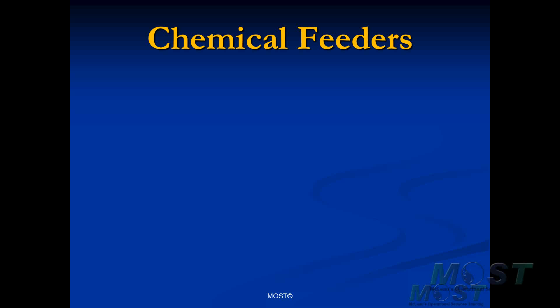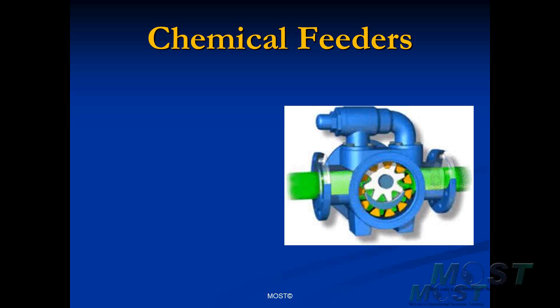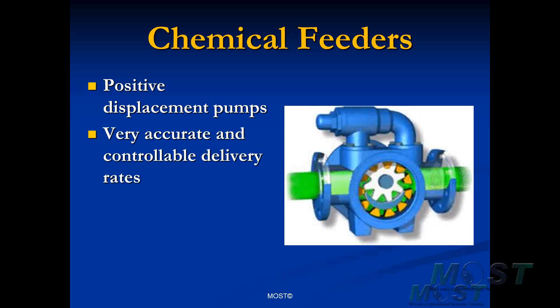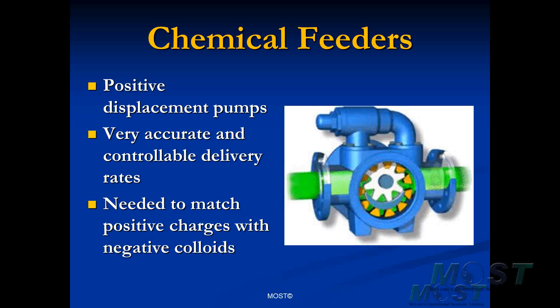To add our primary coagulant to the water, we need a chemical feeder. The typical chemical feeder used for primary coagulants is a positive displacement pump. The reason we choose positive displacement pumps is because they have very accurate and precise delivery rates, and they can be controlled over a wide range of flows. That means that we can deliver exactly the number of positive charges needed for charge neutralization to offset or neutralize the negative charges on the surfaces of the colloidal materials coming into our treatment plant.